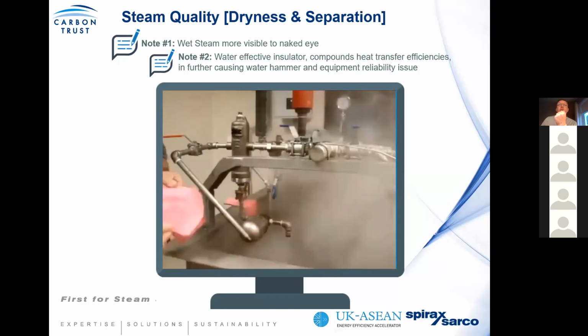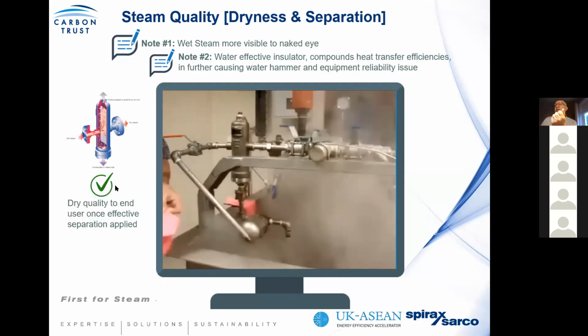Again, it should be understood that wet steam is an insulator. It reduces heat transfer efficiency, increases the likelihood of water hammer, and reduces plant reliability. So through a separator, you have high quality dry steam to the end user. This process can use the full enthalpy of evaporation of steam. So in other words, you can reduce your demand on the steam system when you're using higher, better quality steam. Again, please understand, these are test conditions, and the test was conducted to demonstrate the purpose of the separator.